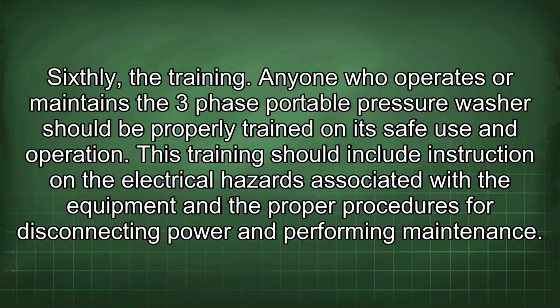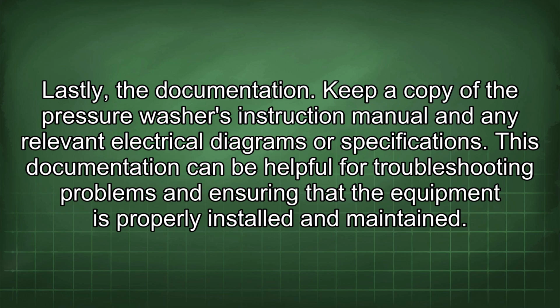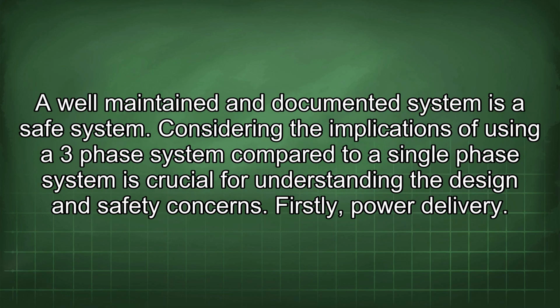Anyone who operates or maintains the three-phase portable pressure washer should be properly trained on its safe use and operation. This training should include instruction on the electrical hazards associated with the equipment and the proper procedures for disconnecting power and performing maintenance. Lastly, the documentation. Keep a copy of the pressure washer's instruction manual and any relevant electrical diagrams or specifications. This documentation can be helpful for troubleshooting problems and ensuring that the equipment is properly installed and maintained. A well-maintained and documented system is a safe system.